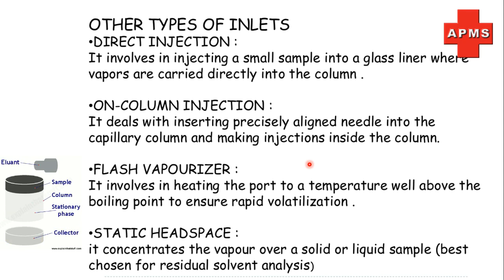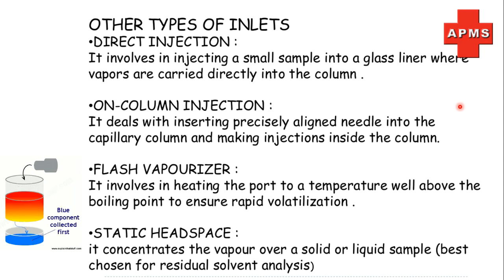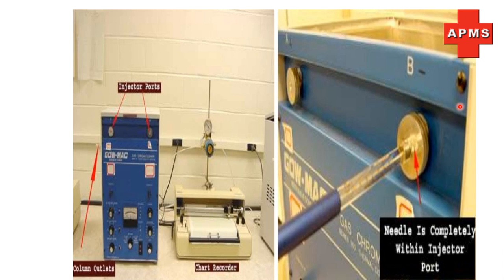This covers all the injection ports of gas chromatography. Thank you for listening to the lecture. Here, a practical example of the injection port is shown — the injection port and the needle from where we inject the sample into the port. This injection port is situated inside the instrument, which is thermostated and remains at a constant temperature during the experiment.